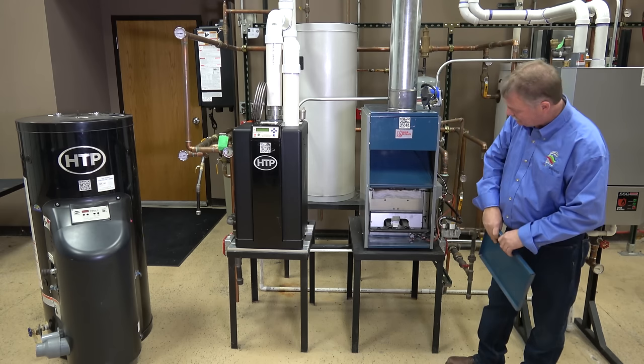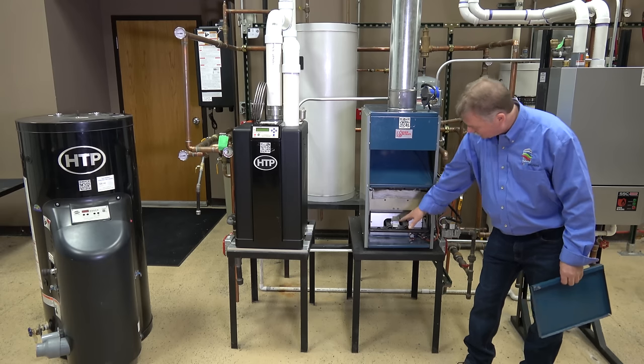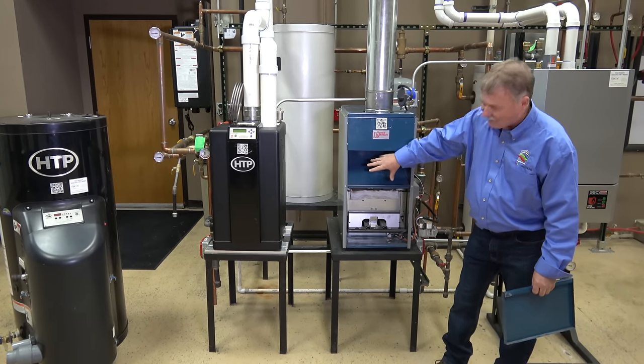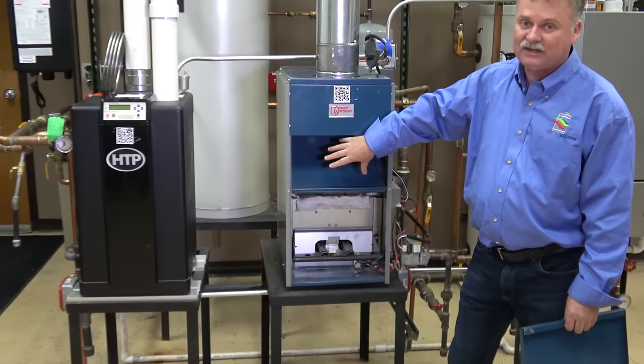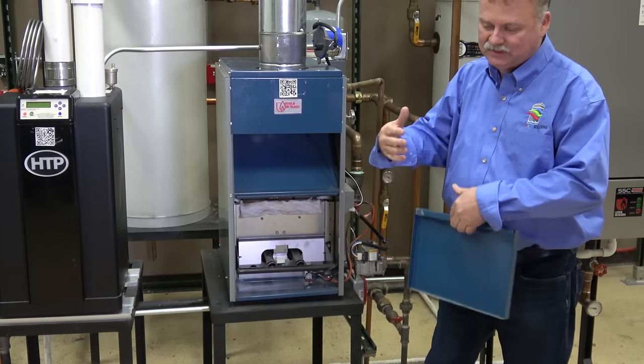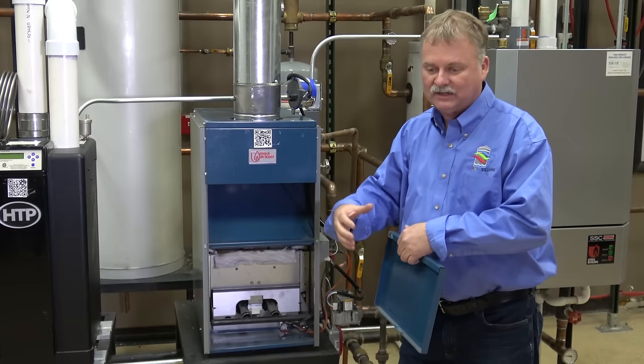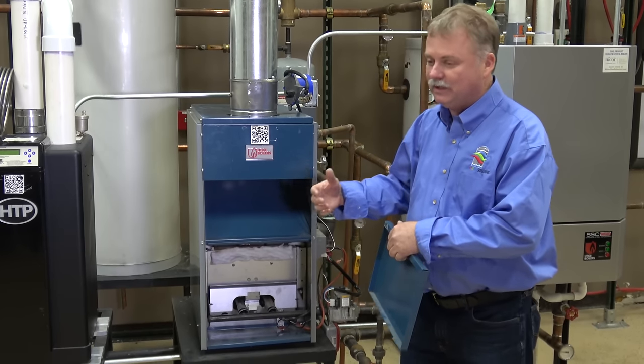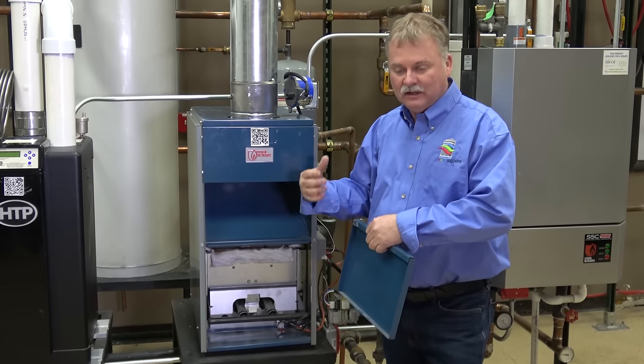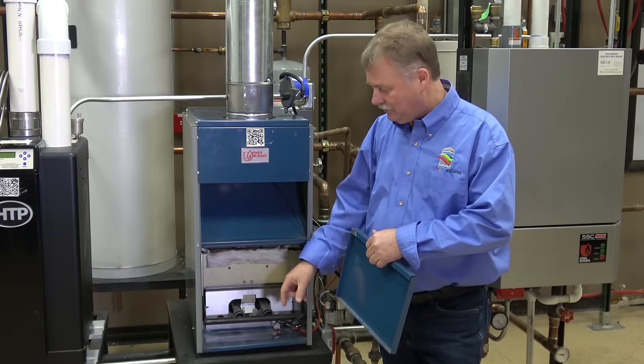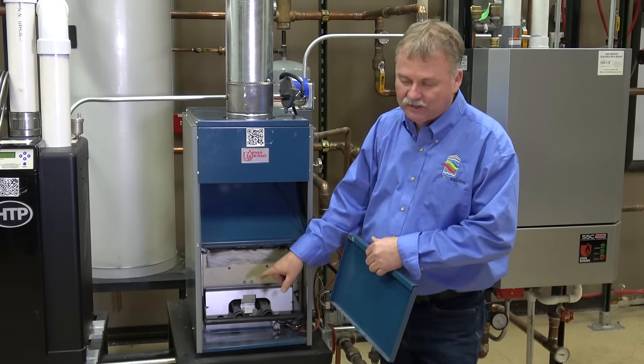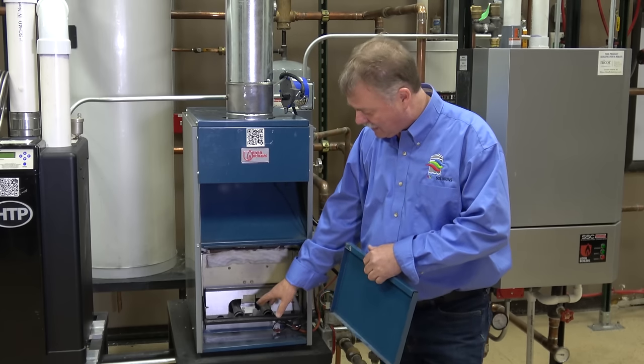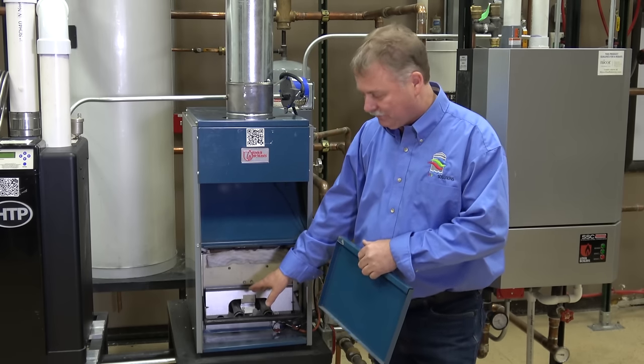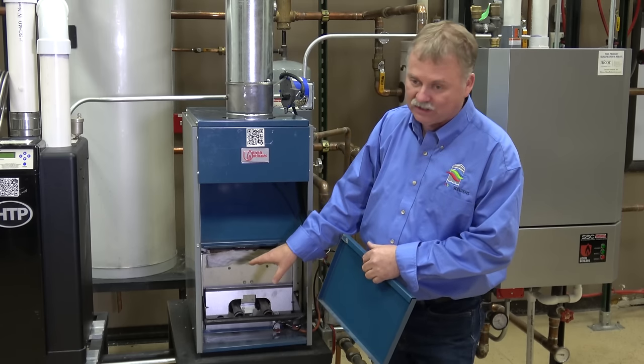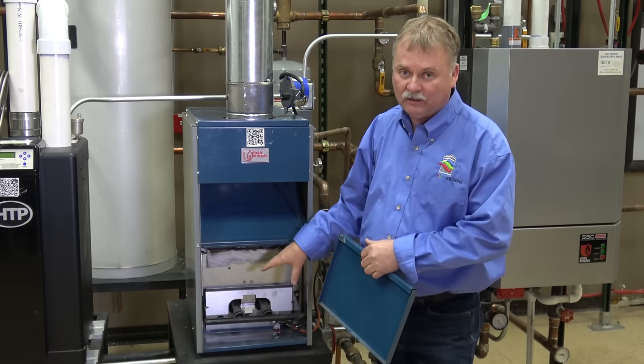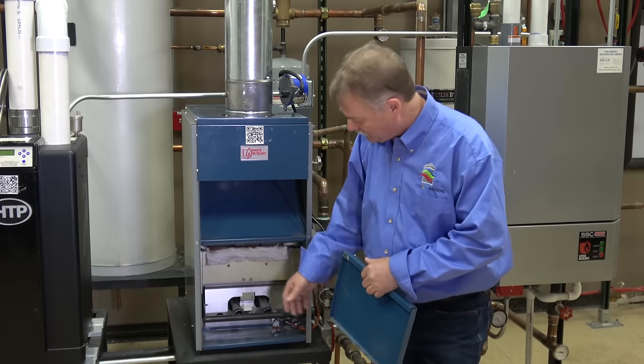In the front section of the unit, basically we have the burners. And behind here, the actual heat exchanger is a full cast iron block. So basically, it's sections of cast iron that are pressed together. In this application, cast iron push nipples. That's where all the water is. In between the sections is the actual heat exchanger, where the gas in the flue goes right up in between those sections and transfers the heat to the water that goes into our hydronic system.